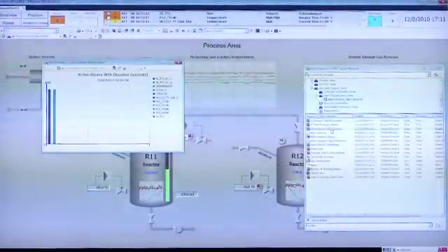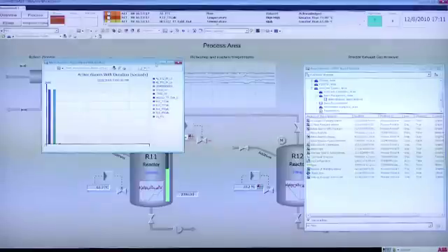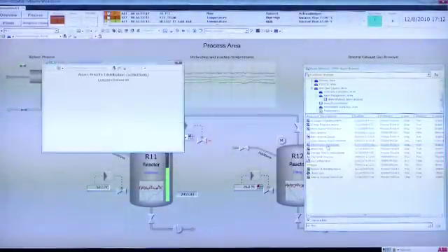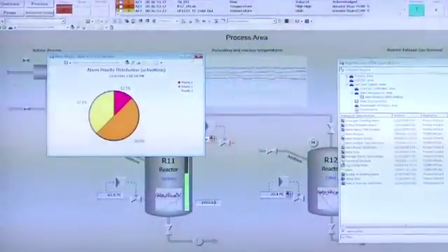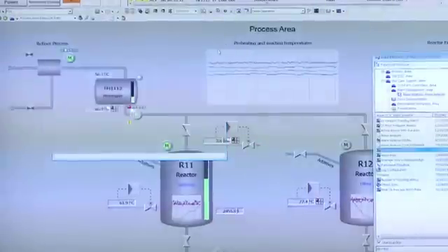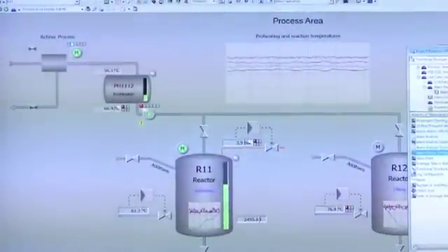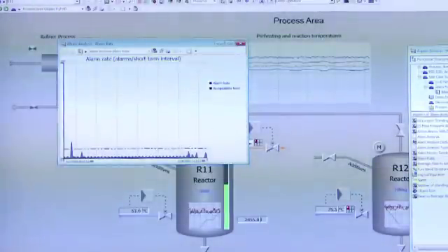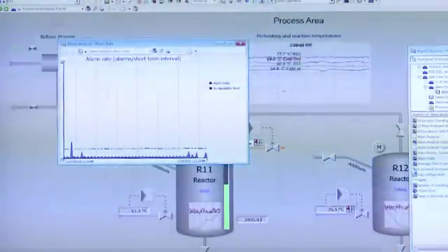Traditionally, alarm analysis meant that you would have a separate alarm and event historian, which would have to be integrated to the control system with a logger connection or OPC AE. With System 800XA's integrated alarm analysis, we just have to point to any alarm list within the system, and the statistics will be automatically generated and displayed via normal Microsoft WPF graphic elements.